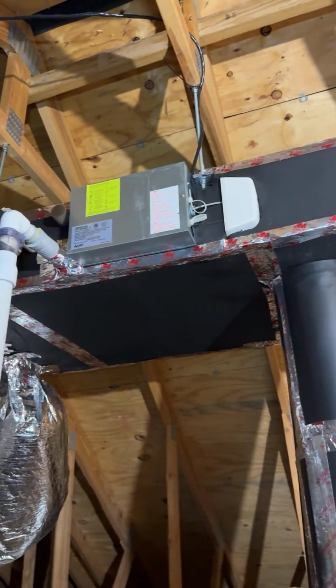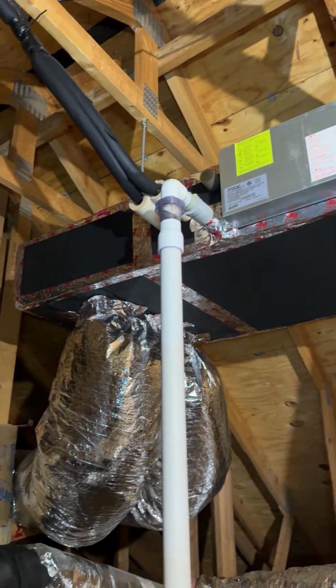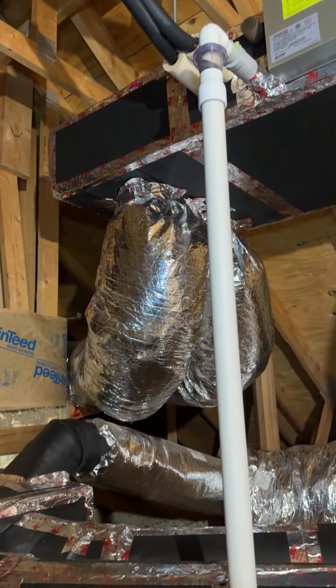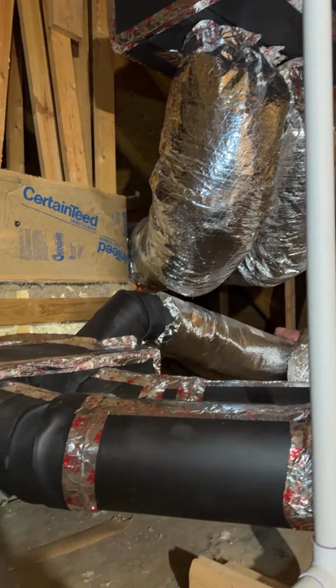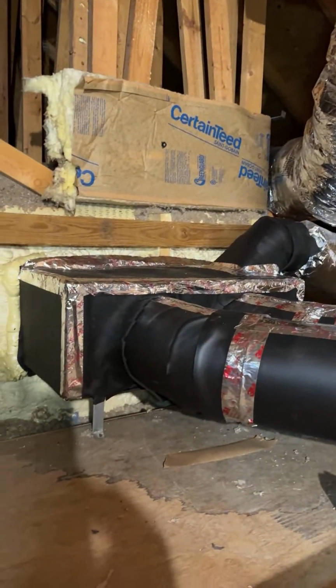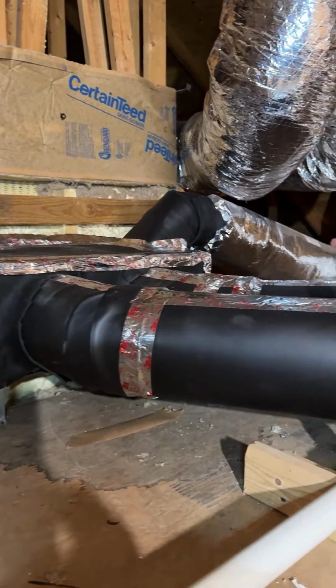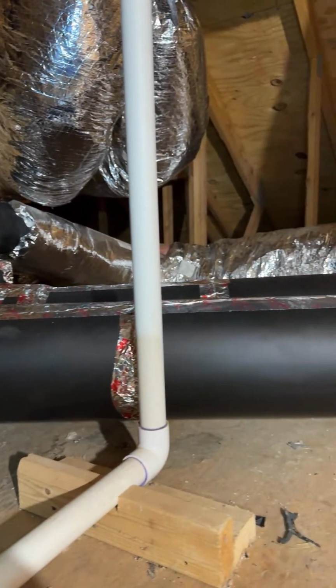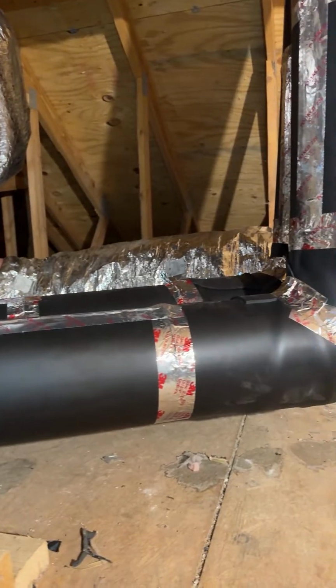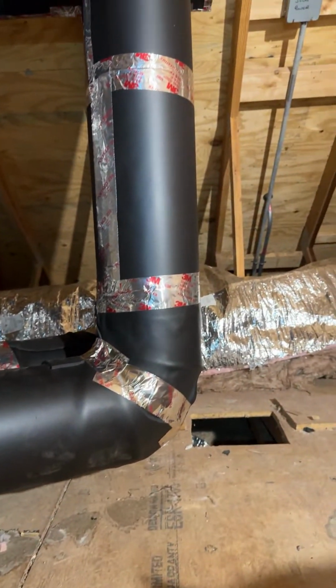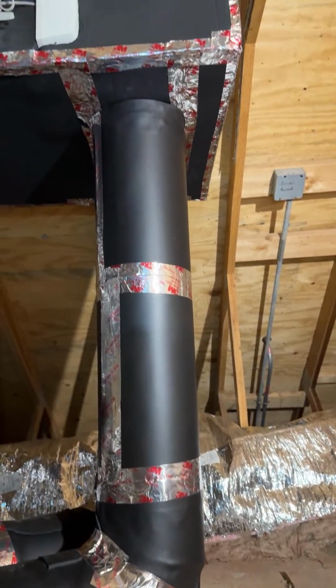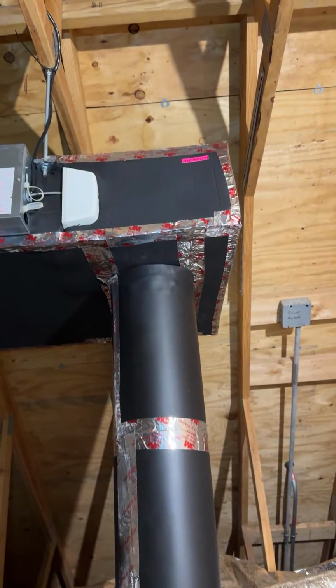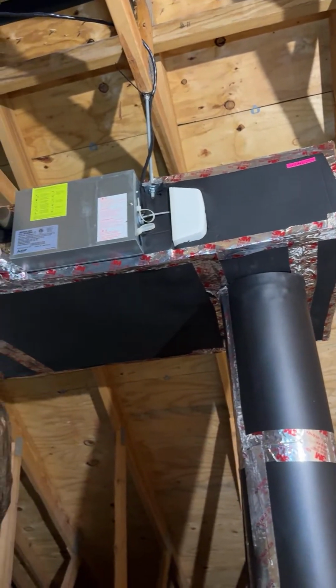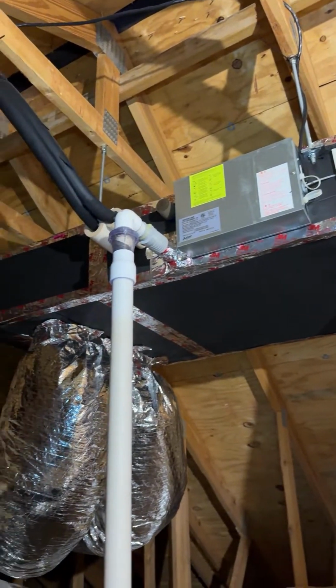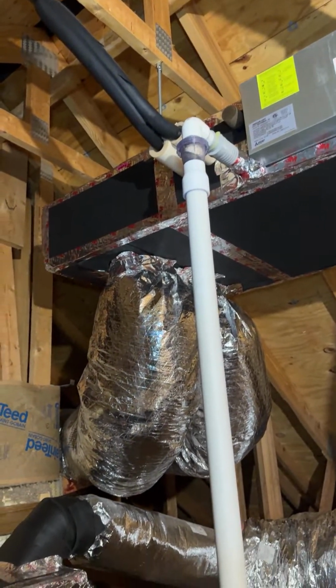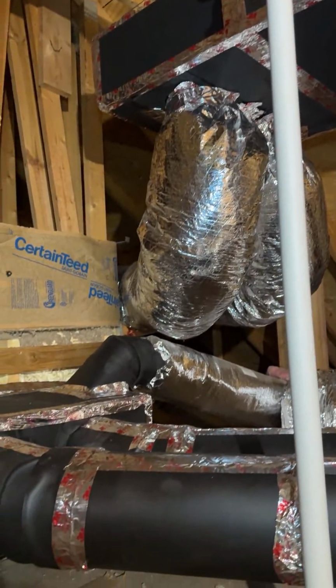And if you ever have to put a system in your attic, make sure that attic is conditioned, is insulated. And if it's not, and you already have a system up there, consider wrapping it in neoprene. It's a much cheaper and actually quite simple alternative to putting in extra insulated ducts. So this was recommended to us by a number of folks, and we're going to see how it works. And this was a DIY job with the neoprene, not running the ductwork. I had a professional do that side.